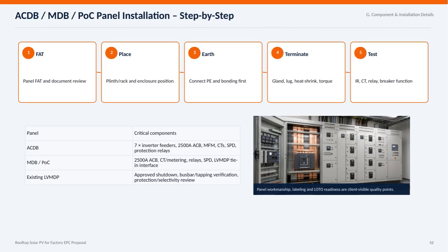Let's walk through the step-by-step process for ACDB, MDB, and POC panel installation, focusing on the key components and installation details. First, we start with the FAT, which includes a thorough panel FAT and document review to ensure everything is in order. Next, we prepare the installation site by positioning the plinth or rack and the enclosure correctly. Then, it's crucial to connect the protective earth and bonding first for safety. After that, we proceed with termination, including glands, lugs, heat shrink applications, and proper torquing. Finally, we conduct comprehensive testing, such as insulation resistance, current transformers, relay checks, and breaker functionality.